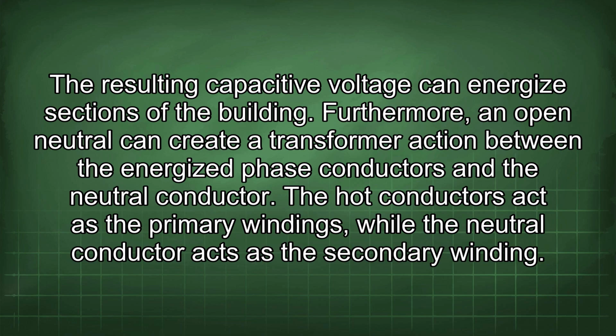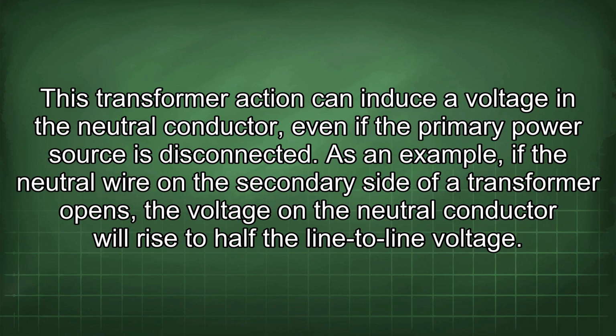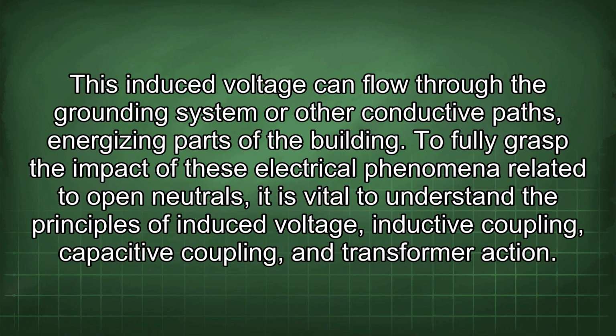Furthermore, an open neutral can create a transformer action between the energized phase conductors and the neutral conductor. The hot conductors act as the primary windings while the neutral conductor acts as the secondary winding. This transformer action can induce a voltage in the neutral conductor, even if the primary power source is disconnected. As an example, if the neutral wire on the secondary side of a transformer opens, the voltage on the neutral conductor will rise to half the line-to-line voltage. This induced voltage can flow through the grounding system or other conductive paths, energizing parts of the building.